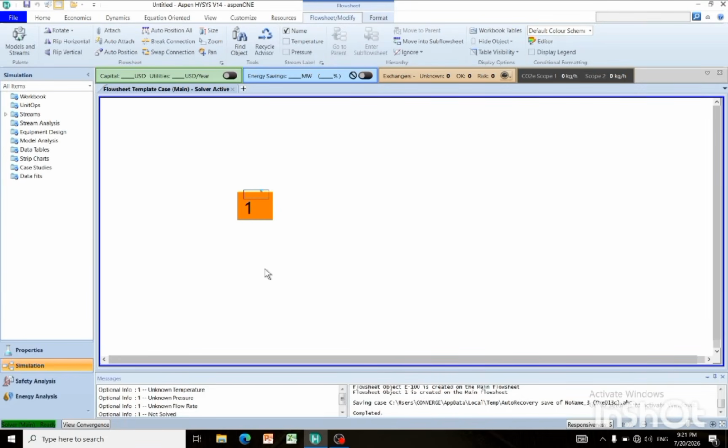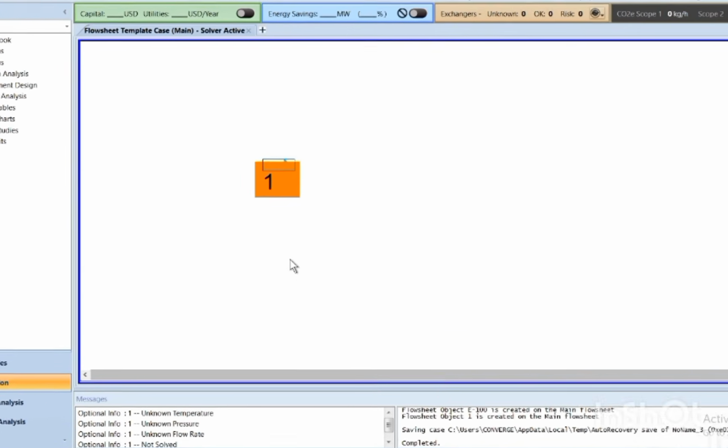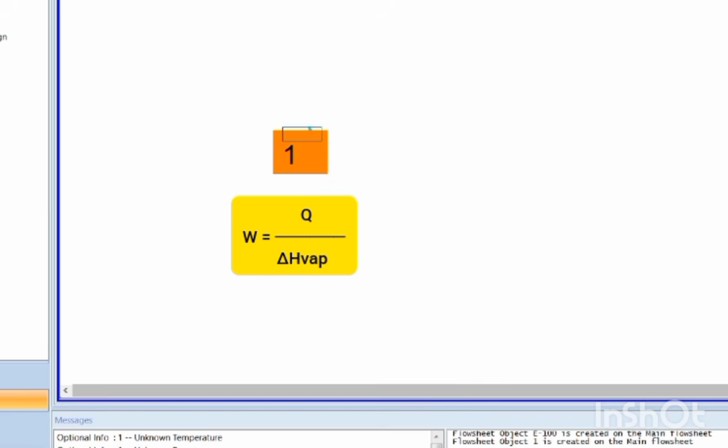As I have discussed, for a fire case scenario, we should find the lambda in HYSYS. It could be quite challenging to find the latent heat for a mixture, because the relief load equals heat absorbed by a vessel per latent heat. We should find the minimum value of the latent heat, which results in the maximum value of the relief load.